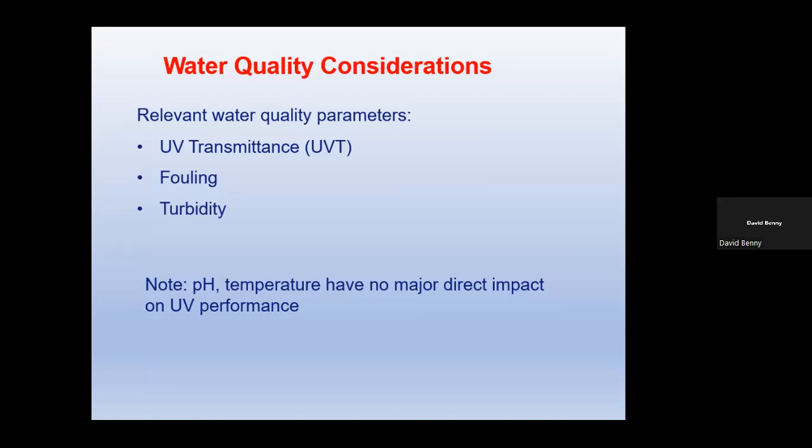If you have metals or colored wastewater, it presents a challenge and the bulbs become fouled. At the Beetham wastewater treatment plant, when it was conceptualized, it was supposed to treat the effluent from Angostura Rum Distillery. Now that is distillery effluent that is highly colored.